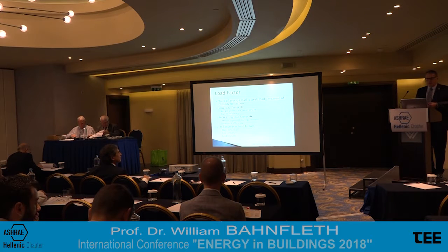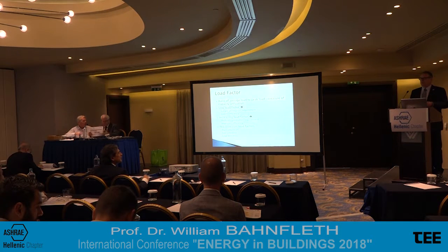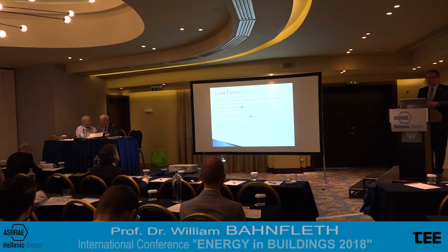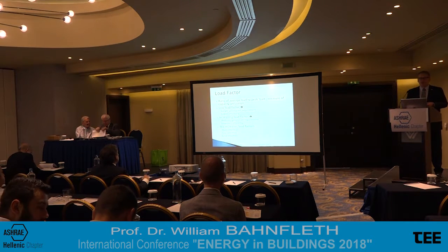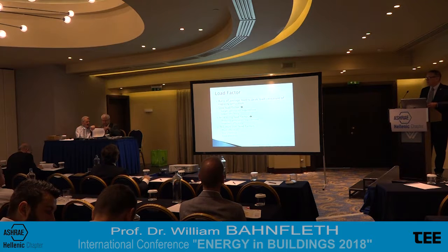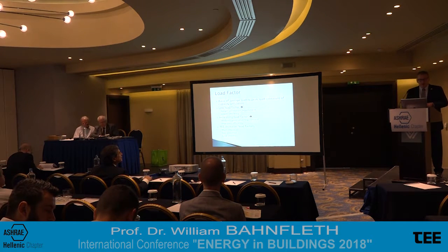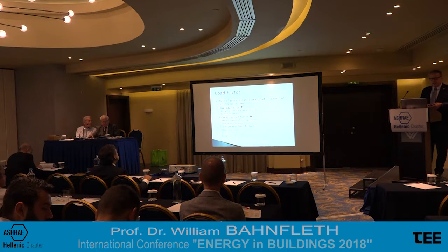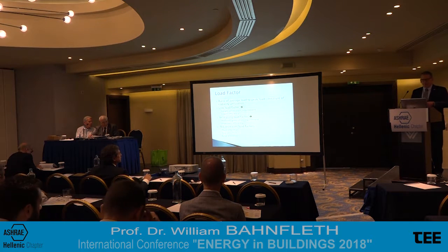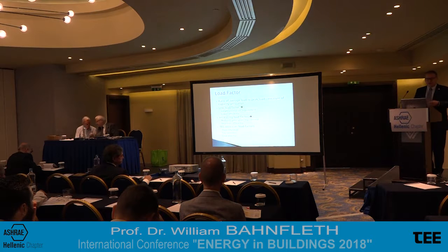When load factors are low, what that means is you have a lot of generation capacity that's not utilized very much. You may have to have a very large electric generating plant or chilled water plant simply to meet a peak load that occurs a few hours in a year, and maybe not even every year. If we can do something to increase a load factor, then the plant size and cost becomes smaller, and it tends to operate more efficiently, as I've said.